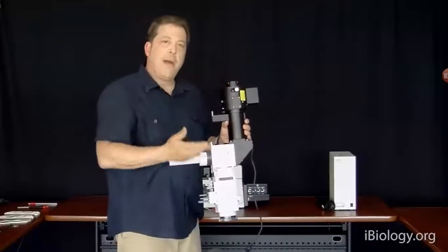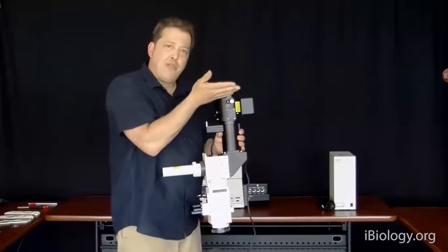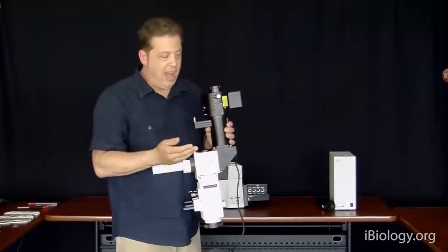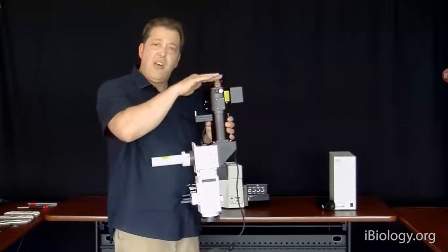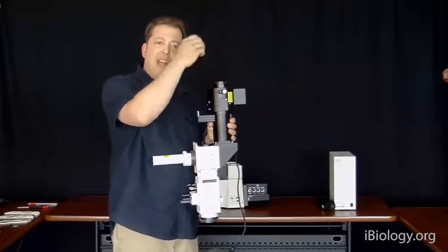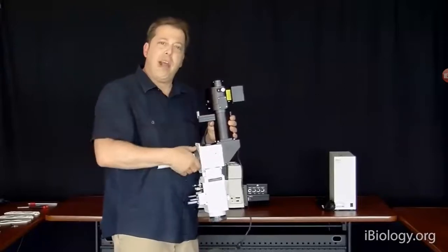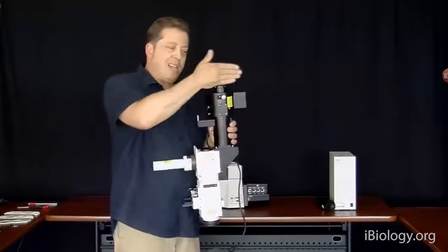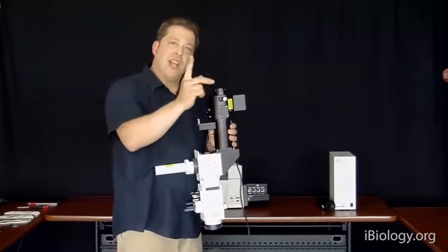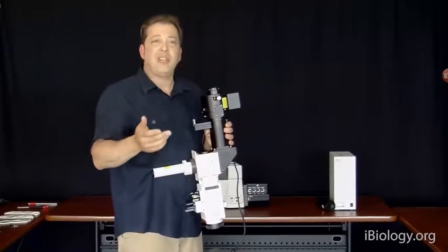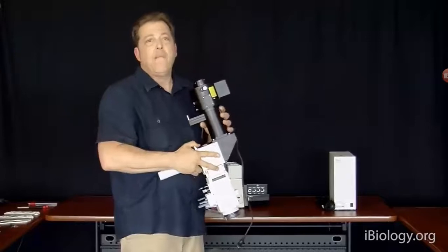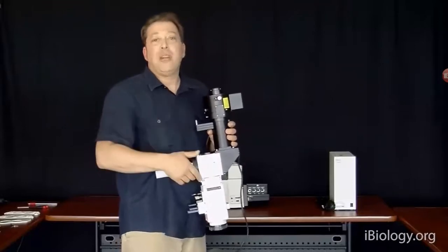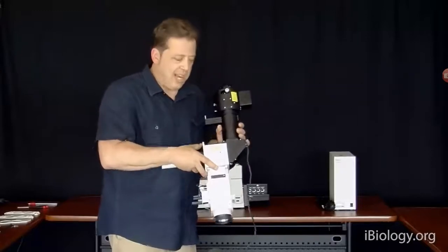The fiber tip here, again, going back to aperture and image planes, is actually sitting right at an aperture plane. And we know that in the case of total internal reflection fluorescence, you need to get a collimated beam of laser light out of the objective. And we do that by taking this aperture plane where that fiber tip is, and then relaying the core of that fiber tip to the back aperture of the objective lens. And we focus that with this switch here so that we're focused. And then when we translate that fiber in X and Y, it moves that focused laser beam in X or Y at the back aperture, and that changes the angle that the light comes out in image space, because lateral translation in aperture space relates to an angular translation in image space, as we've talked about in previous lectures.